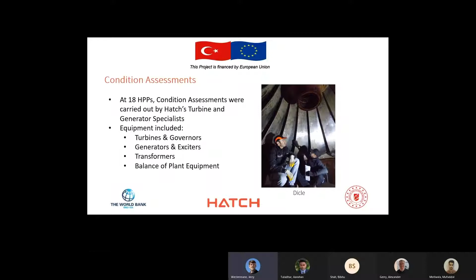The condition assessments were carried out at 18 of the 22 hydropower plants, and as I indicated before, Hatch's turbine and generator experts, mechanical and electrical engineers, visited these sites and were usually able to enter the turbines to see the condition of the runners, as you see in this one photo. In addition to the turbines and governors and the generators and exciters, we also conducted condition assessments on transformers, as well as balance of plant equipment such as ventilation systems and overhead cranes and so on.